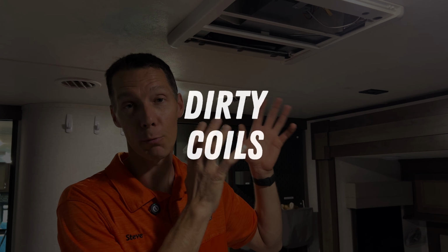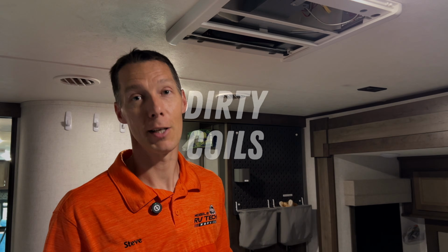Maybe it's an undersized AC unit, and all it can do in the heat of the day is just barely maintain a temperature, and it won't cool down until the nighttime. Or it could be some issues like dirty coils in the AC unit on the roof itself. So let's go up there and check it out.